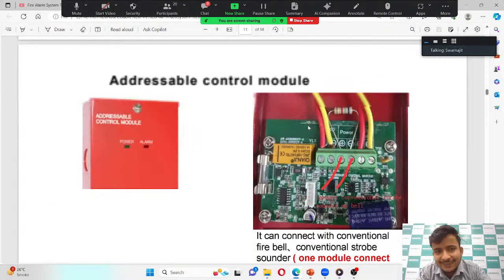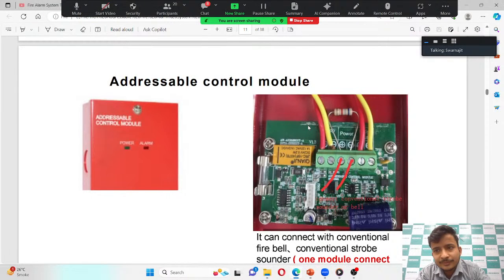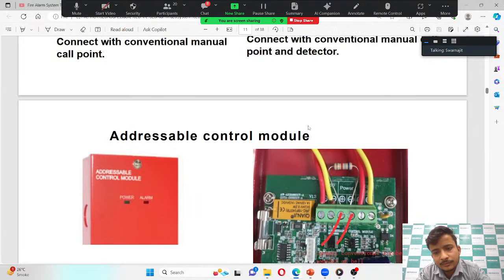I have one more question. Do you have any scope of redundancy in this fire alarm panel system? Like if your CPU fails, are there any options? If your CPU fails, we can provide software redundancy. One software works as the primary server and another works as the secondary one. So if your CPU fails, the secondary one will automatically take over. But that will happen at the software level, right? Software level only, not at the panel level. Is this software yours, or a third party's? It is our own only.